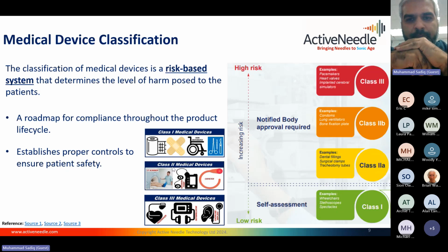Medical device classification. If you are a manufacturer of a medical device and plan to market your product in either the US or EU markets, you have to classify your medical device according to the rules of the respective regulatory agencies. And I'll come to the regulatory agency bit in the next slide. The classification of a medical device is a risk-based approach that determines essentially the level of harm posed to the patients.